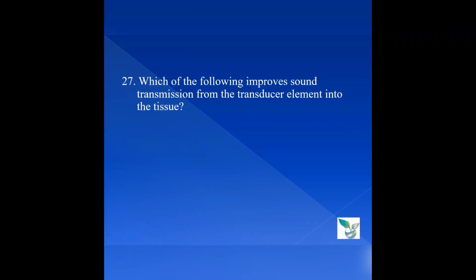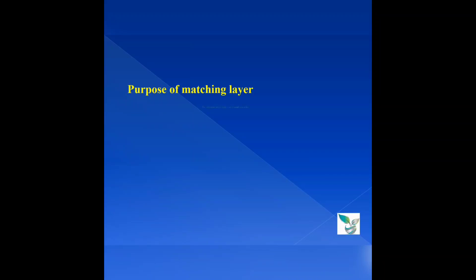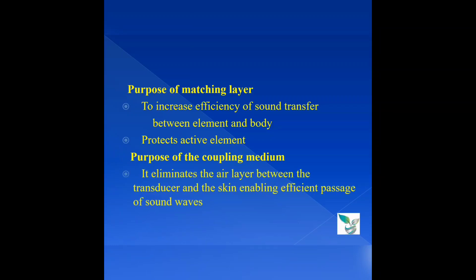Moving on to question number 27: Which of the following improves sound transmission from the transducer element into the tissue? Option A, matching layer; option B, Doppler effect; option C, coupling medium; option D, both A and C. The answer is both A and C. The purpose of the matching layer is to increase the efficiency of sound transfer between the element and body, and to protect the active element. The purpose of the coupling medium is to eliminate the air layer between the transducer and the skin, enabling efficient passage of sound waves.